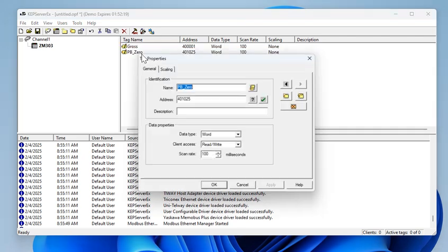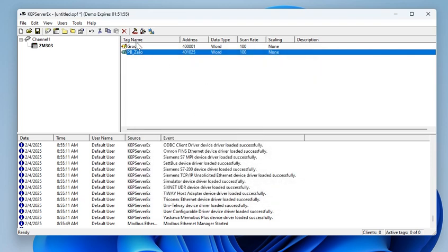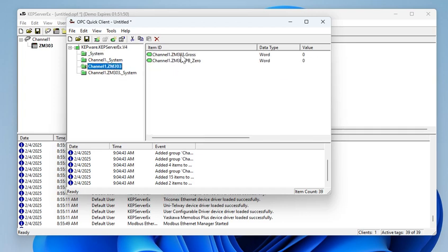And also the other tag, for zero scale, is 41025 on the indicator side. In this software, if you enter 41025, it will automatically change to 401025. So press OK, then you run it. Press OPC, then you can choose the weight. This is the weight. I change the scale side, and you can see the weight change, same as the indicator.